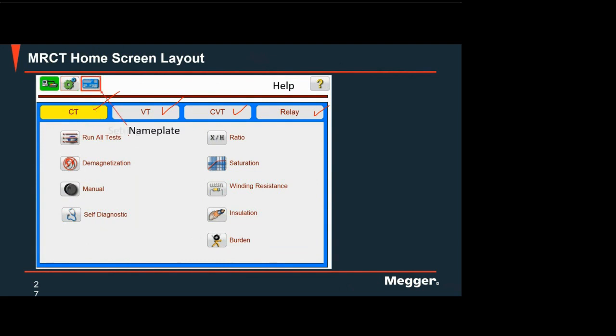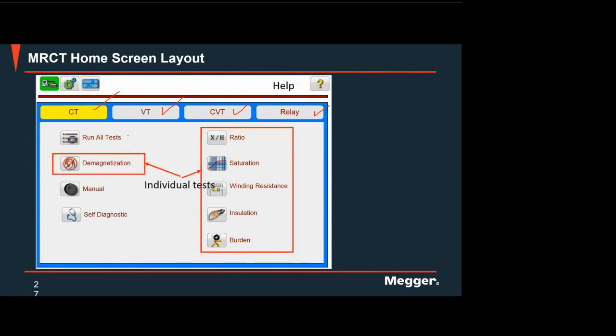This is the setting tab. This is the nameplate tab. The test functions. So you can also do individual tests. If you want to go directly to the ratio, then no problem. If you want to go to the saturation, no problem. But the good thing with the run all test is that it will do a sequential test. It will do the tests in sequence.